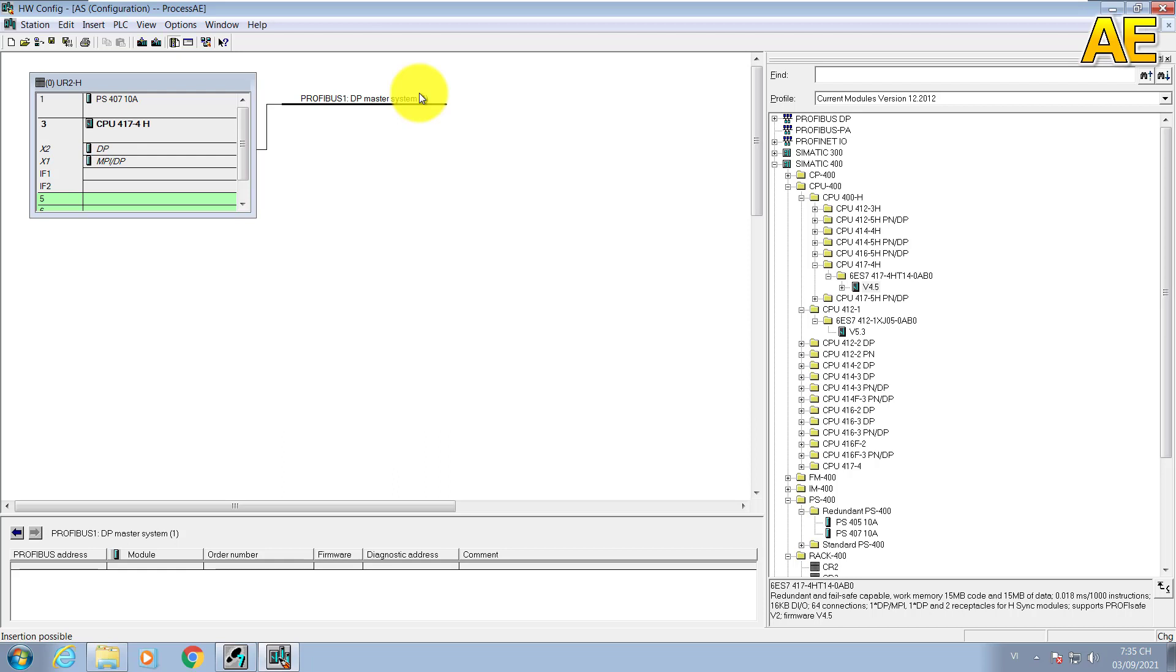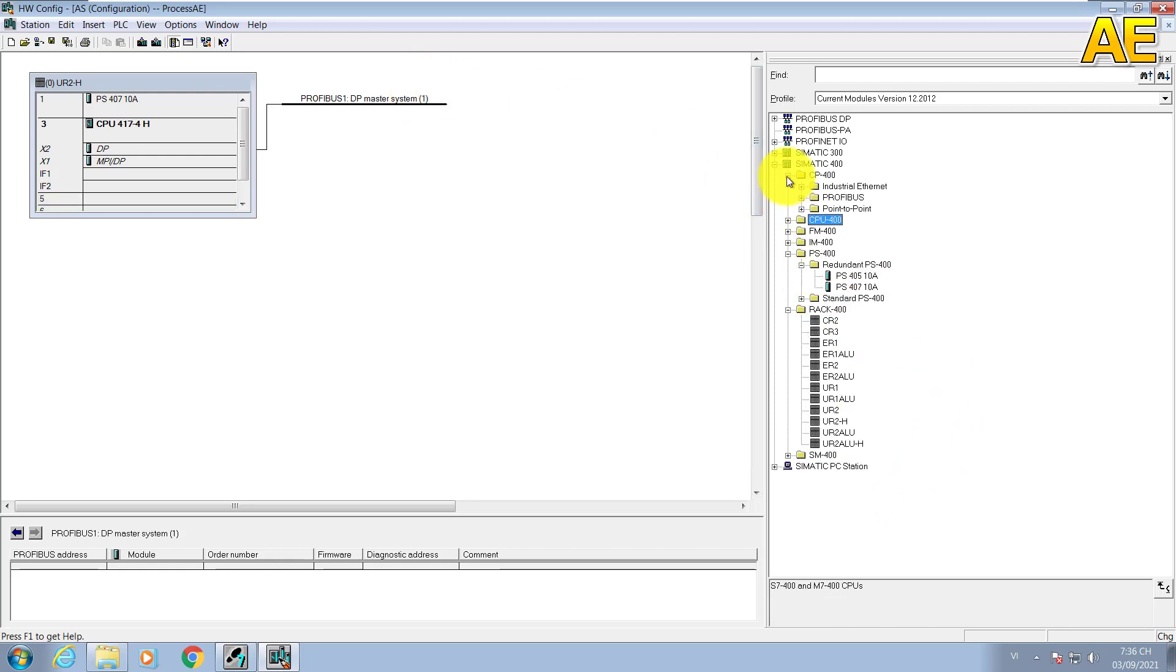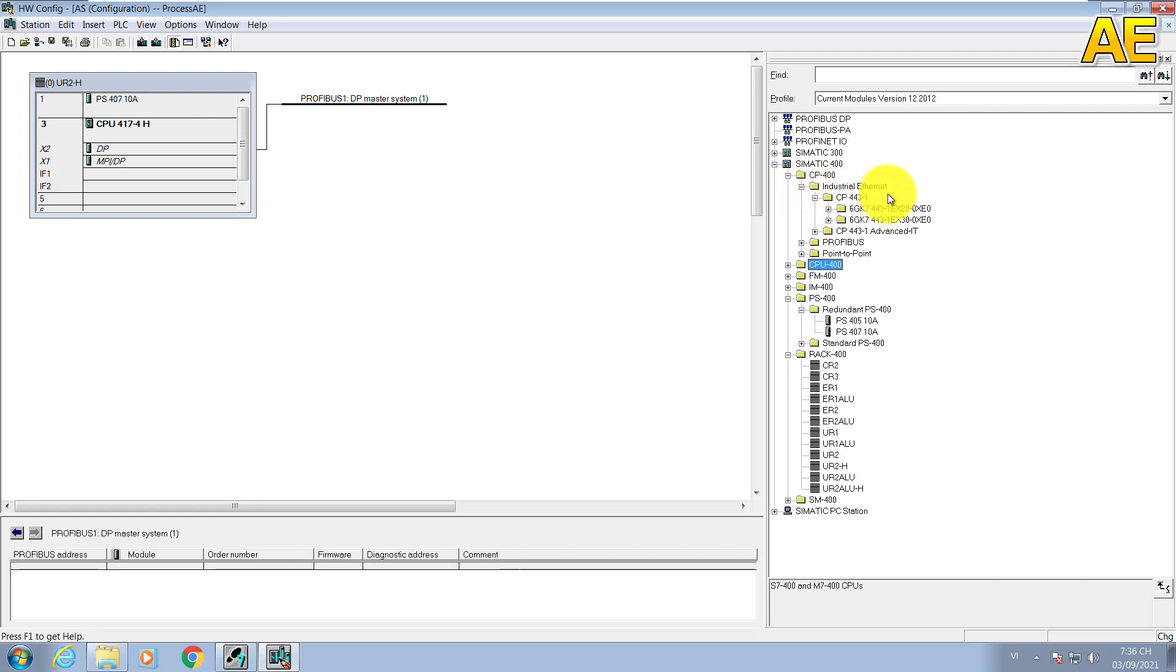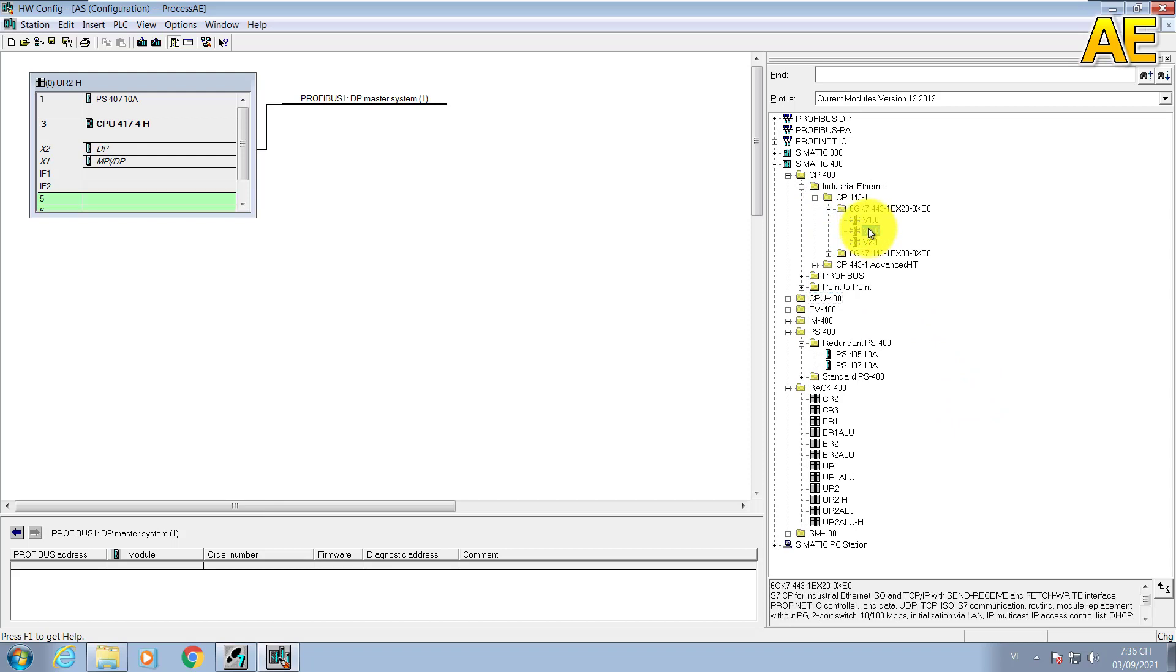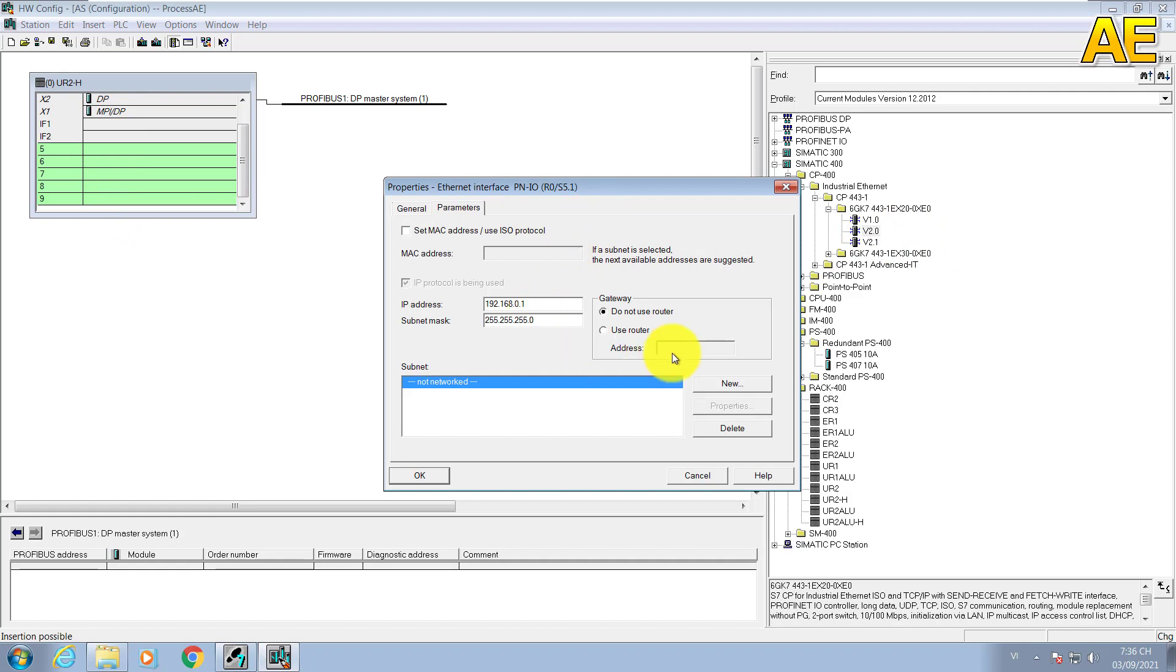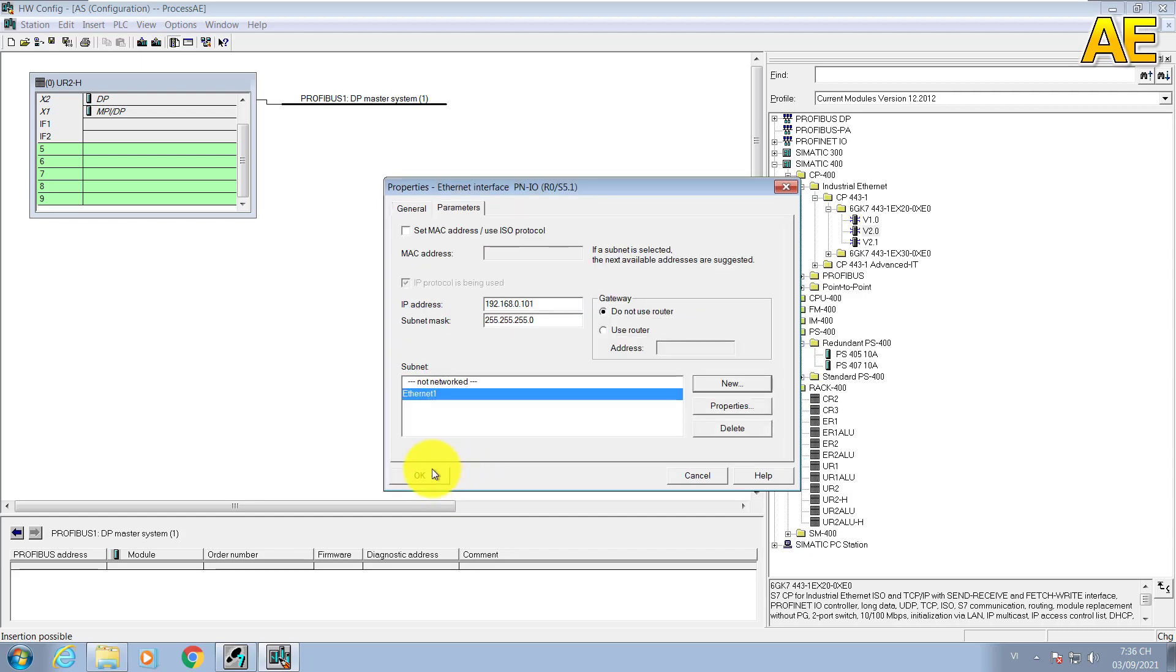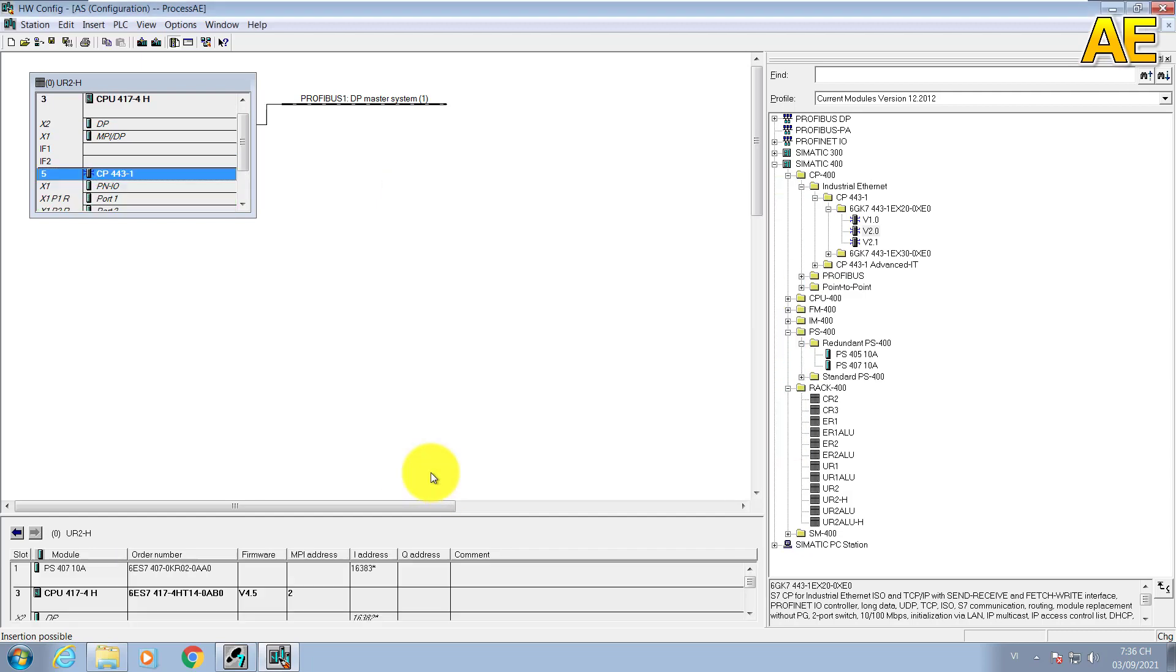Next step I need to select one processor for Ethernet communication. We come to CP400, CP400 here, come to Ethernet here, CP443-1. I will select the version 2.0. This config for the Ethernet network. First, I will change IP 101 and click New, the Ethernet 1, and Subnet ID let's default.